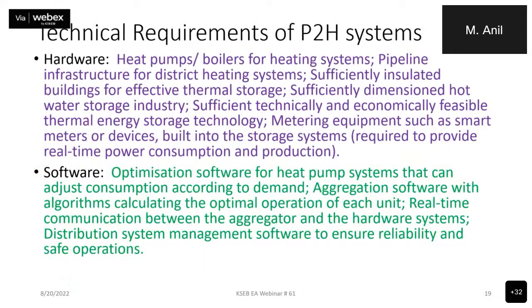Technical requirements for power to heat systems: hardware, heat pumps, boilers for heating systems, pipeline infrastructure for district heating systems, sufficiently insulated buildings for effective thermal storage, sufficiently dimensioned hot water storage, sufficient technically and economically feasible thermal energy storage technology, metering equipment such as smart meters and or devices built into the storage systems required to provide real-time power consumption and production.